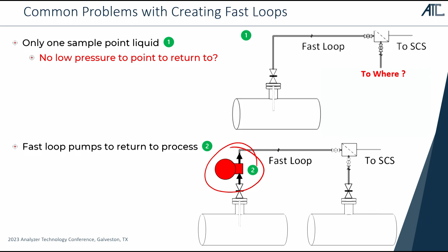It's easy, right? Well, as soon as we put in a pump, we have a whole bunch of issues that can potentially arise with that. First of all, process pumps are going to be expensive, so we'll have costs associated with the pump. We'll probably have a lot more maintenance because pumps require maintenance. I frequently, when looking at analyzer installations, say I don't like to put pumps in because I make my analyzer mechanics become pump mechanics - they're fixing the pumps all the time. There's also going to be a sizing issue.